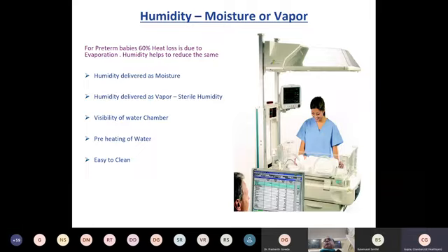It cannot carry to the chamber. So we have done some special tests: we put the most difficult microorganism in the water chamber, and we tried to find out after 7 days whether anything can come inside the main environment. We found that it's almost like a sterile environment; nothing could come.